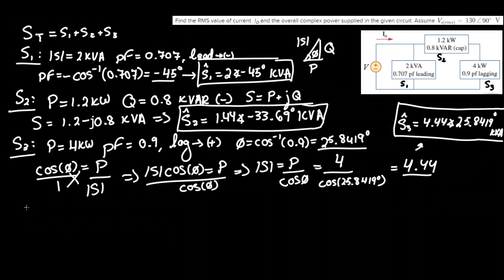So now let's apply that property again where S_T equals S1 plus S2 plus S3. I'm going to rewrite that for clarity: 2 angle negative 45 degrees, this is in kVA, plus 1.44 angle negative 33.69 degrees, plus the final load 4.44 angle 25.8419, this is all in kVA, where the sum is equivalent to 6.6142 angle negative 2.406 degrees kVA.